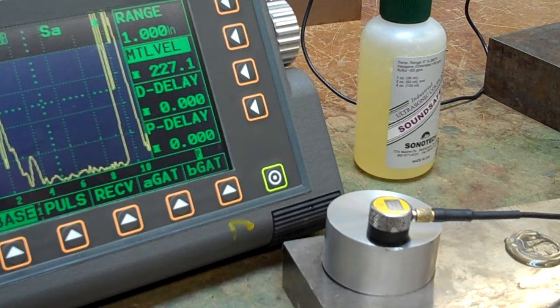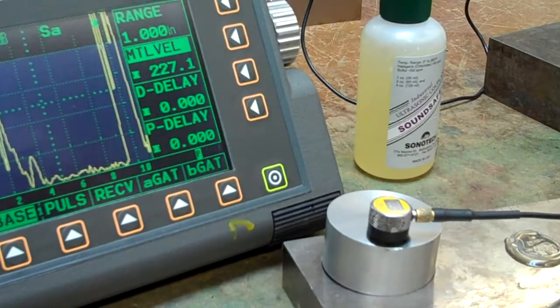So we know this is steel and this is aluminum. But really what we've done is figure out that if we were scanning a piece of steel and suddenly had a velocity change, while the thickness stayed the same, and our signal changed, we'd know we're no longer on steel. So the lab is pretty simple - all you're doing is calculating from one velocity to the other, and you can apply that to anything.